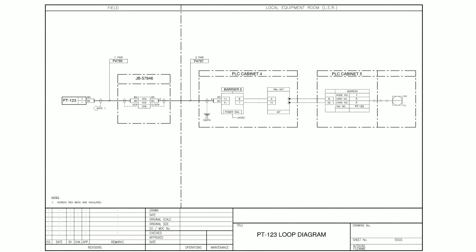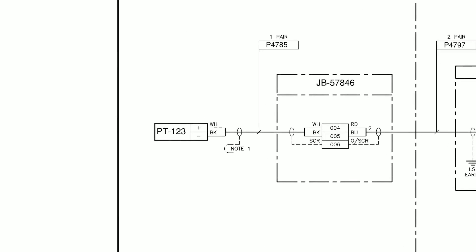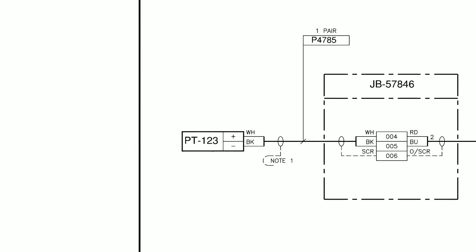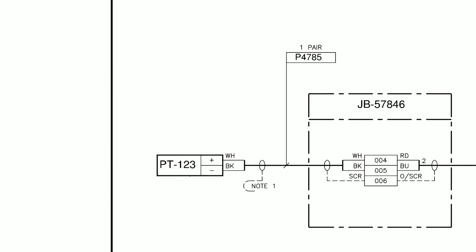Okay, next let's look at the field device over on the left hand side of the drawing. In this case, our transmitter PT123. From our loop diagram, we can see that this is a two-wire device, and likely a 4 to 20 milliamp device, although we can't be certain from this drawing. This could also be a voltage input, but as it's a two-wire device, most modern devices going into analog inputs are 4 to 20.